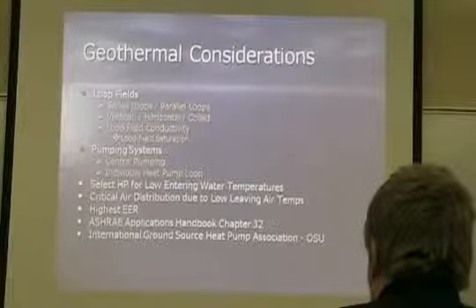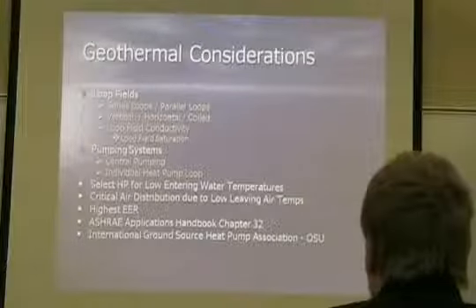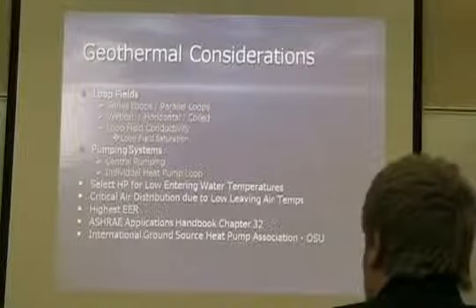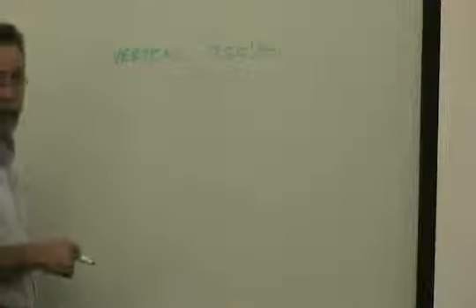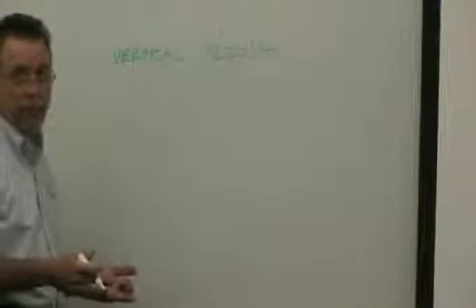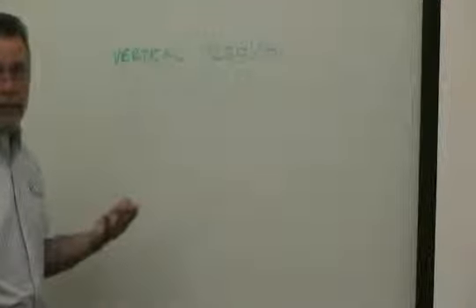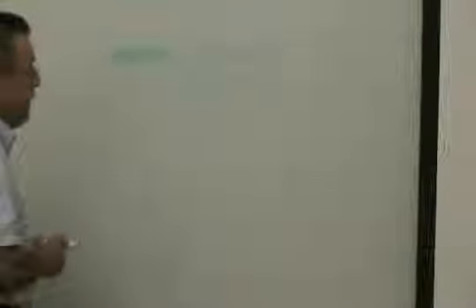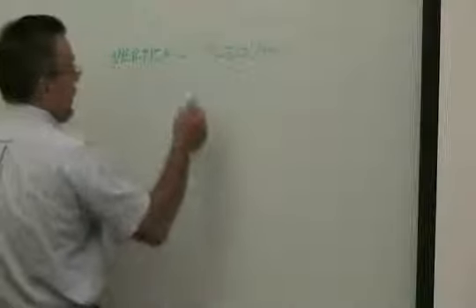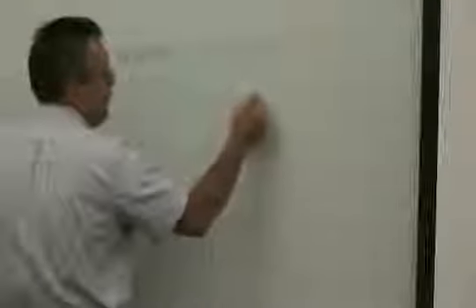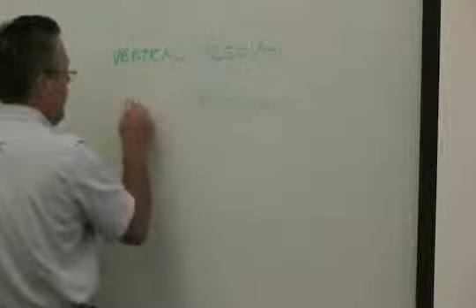But they had series and parallel loops, vertical, horizontal, and the coiled or slinky. And the loop field conductivity determines your amount of loop. The standard rule of thumb for a vertical well is 250 feet per ton. That's a rule of thumb. It can get worse or better based on your conductivity. The only drawback to this geothermal system is I might do a conductivity test today, and five years from now my water's been rediverted by something that's happened either geologically or through construction. So there's some safety factor that you want to put in. That goes up to about 375 to 500 feet per ton for horizontal in those 5 foot deep ditches.